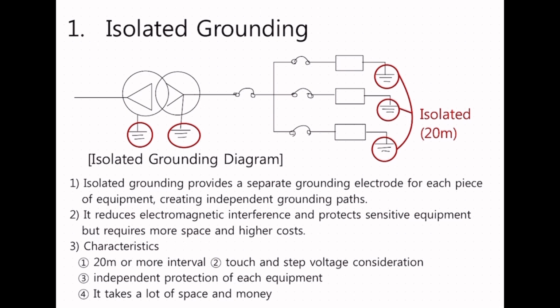Characteristics. 1. Requires adequate spacing between grounding electrodes, typically 20 meters or more. 2. Considers human safety by accounting for touch and step voltage. 3. Provides independent protection for each device from surge currents. 4. Suitable for protecting equipment sensitive to noise or EMI. 5. Requires more space and can increase costs due to the installation of individual grounding electrodes.